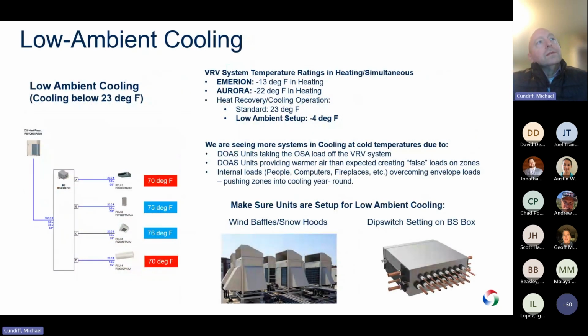Low ambient cooling. So this is a surprising one. A lot of times for cold climates, especially, you'd think that all the fan coils are going to be in heating as soon as it gets below maybe 40 degrees outside or something. But we'll go through the specs first, and then we'll talk about, in my opinion, what some of those factors are that are leading to units being in cooling more than you would expect.